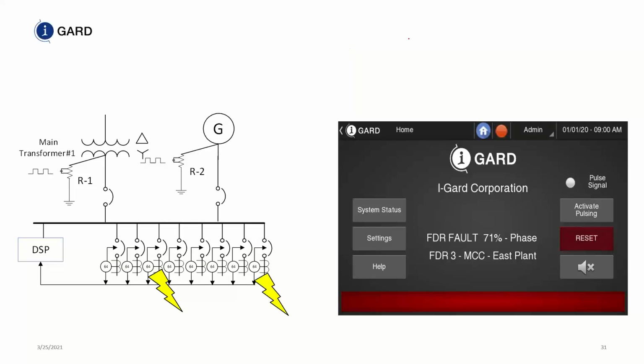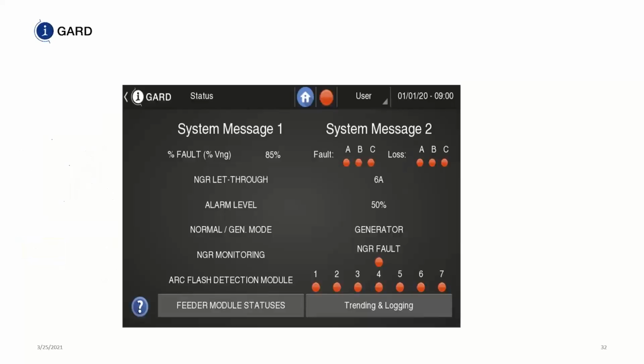But if you get a second fault on a different feeder, on a different phase, then we say there's a fault on two phases. These two modules communicate with each other, and the one that you program to be of a lower priority will trip first, keeping your critical processes going all the time. This is why we use high resistance grounding systems in data centers, in hospitals, in pulp and paper facilities, in petrochemical facilities. You can have monitoring, everything at a glance. You can monitor the integrity of your system's health.